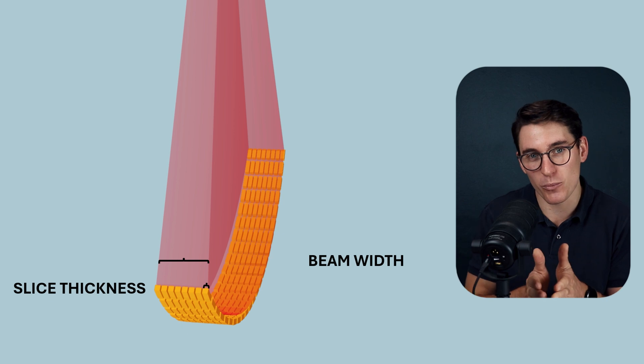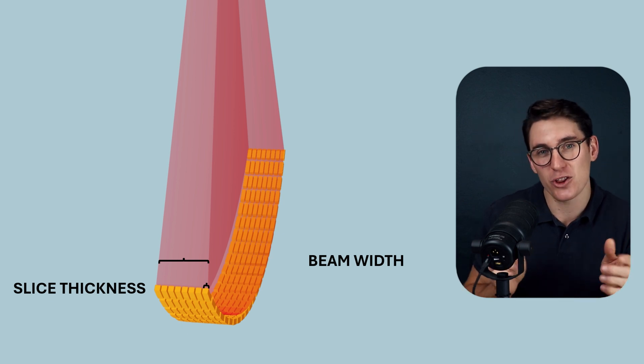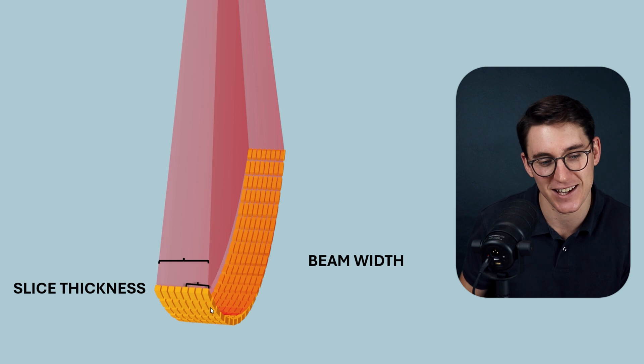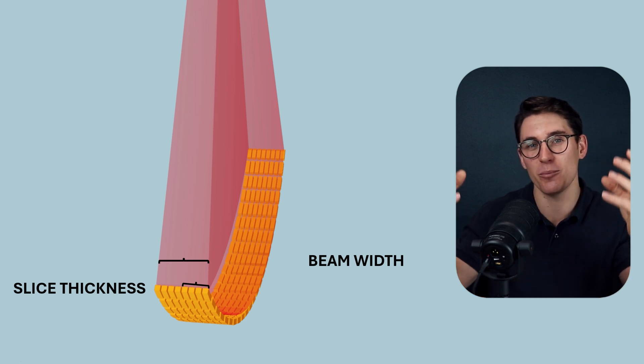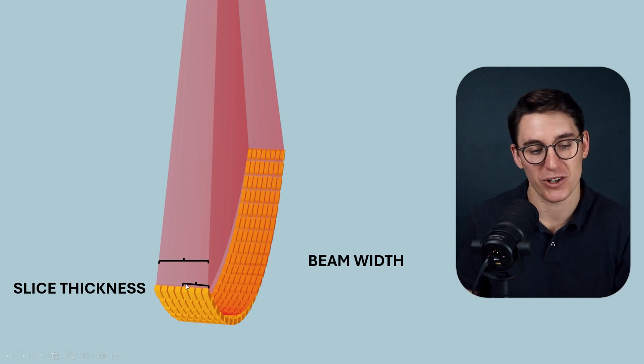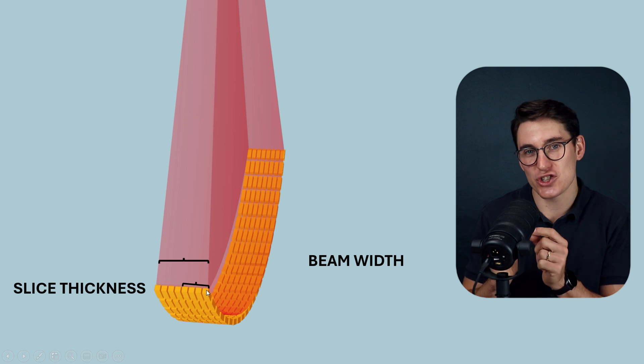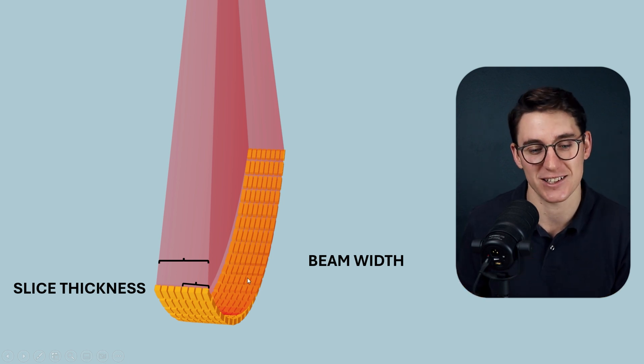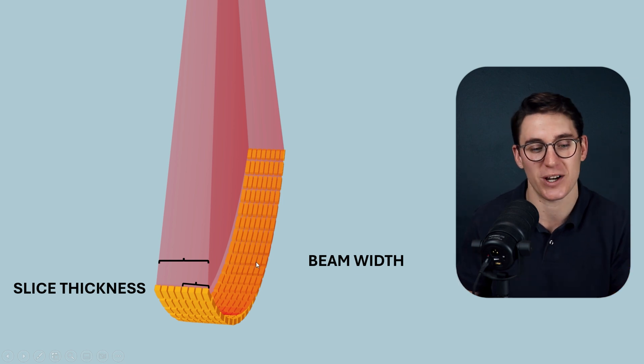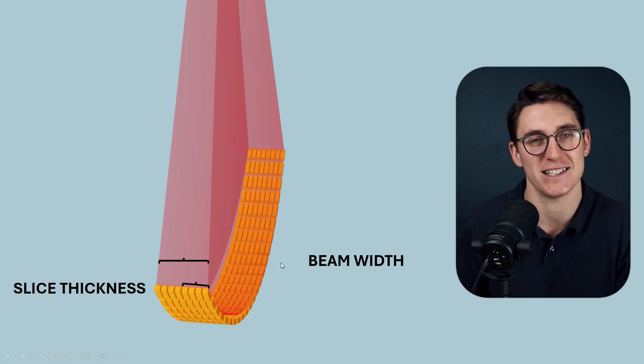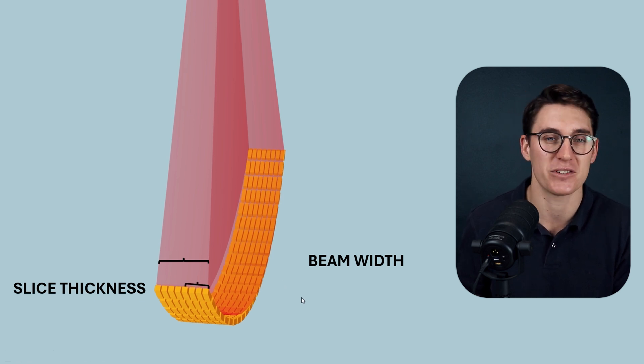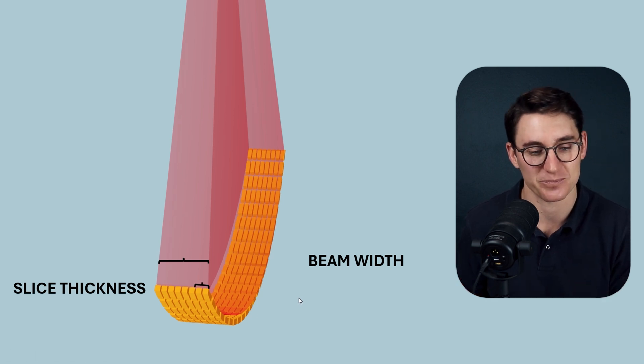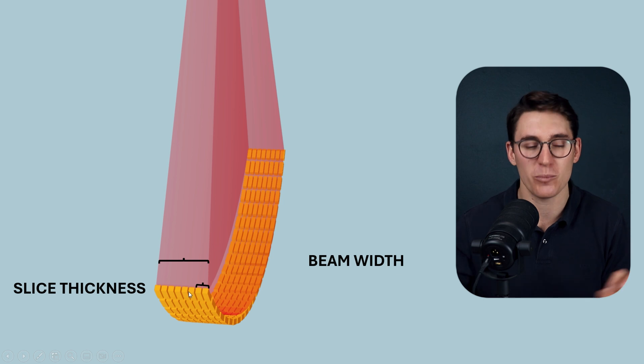If we want more signal, we can bin those detectors together — group adjacent detectors and count them as one — so we're getting more signal and a better signal-to-noise ratio. It's the width of the detectors used to generate a single slice that determines the slice thickness, not the beam width we've collimated onto our detectors. This is a function of multi-detector CT. The slice thickness can change depending on the number of detectors used to create each axial slice. It's incredibly important to understand the difference between beam width and slice thickness.